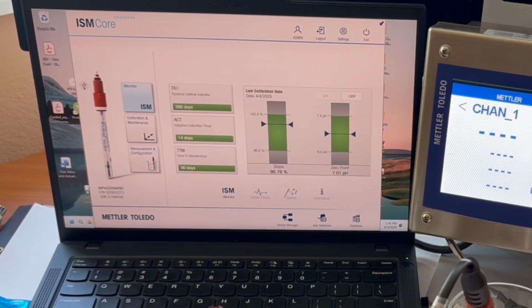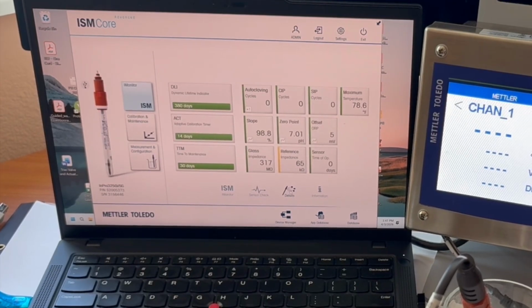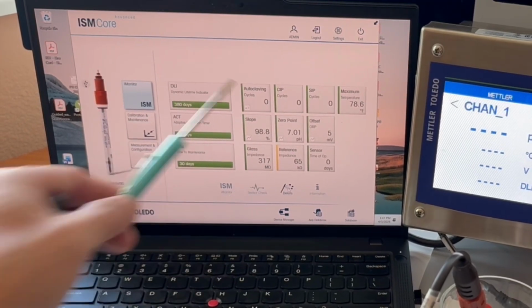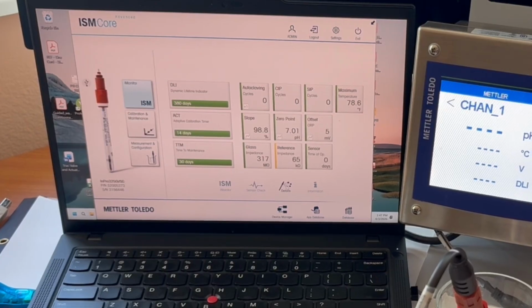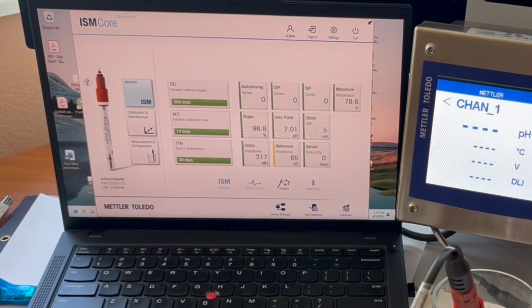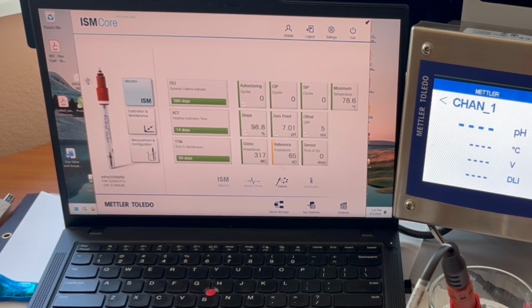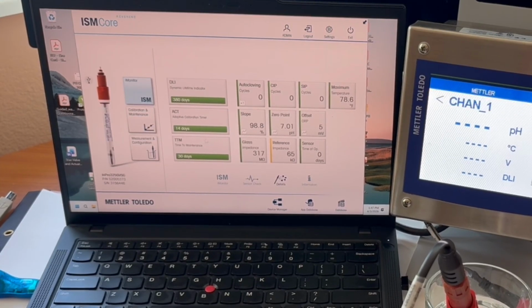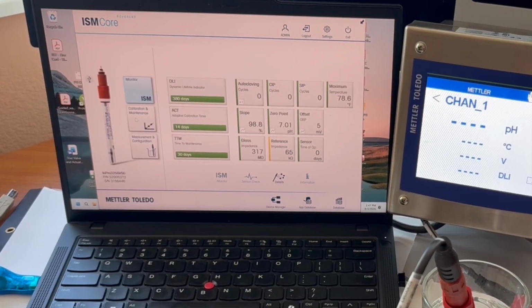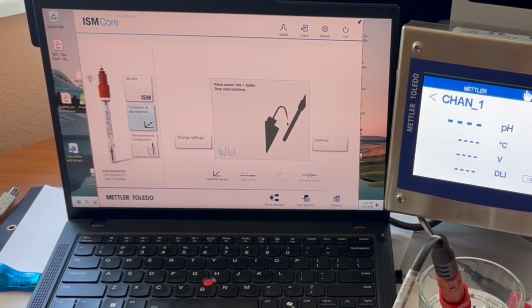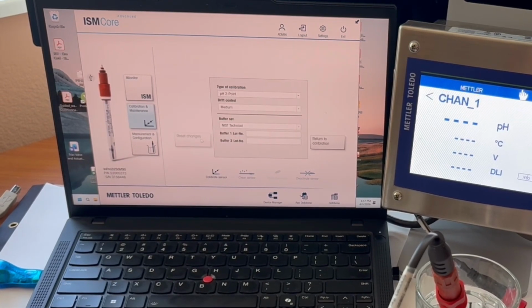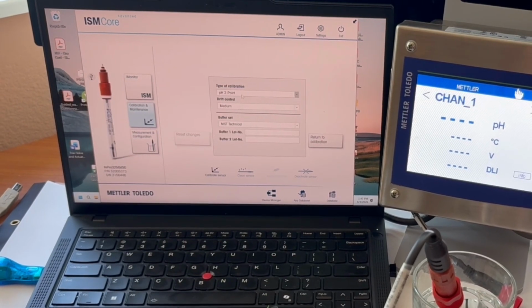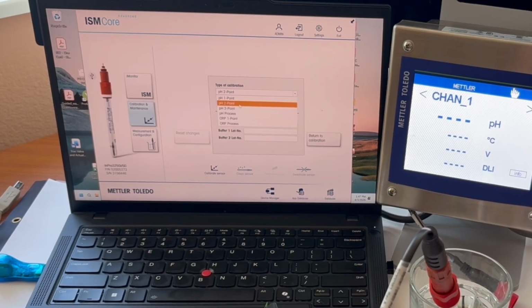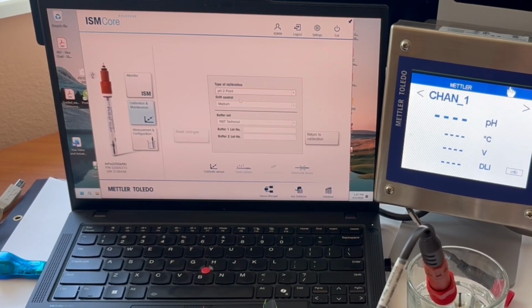Same with the offset. If we go back to details, we do have a yellow indication on the reference. We can determine what that is in a second. But the program literally will show you immediately what's going on with this sensor. The idea here is to do a calibration. So we're going to go right here into this. We'll look at what the settings are. We're going to do a 2-point calibration, but you can see other calibration menus that are available.